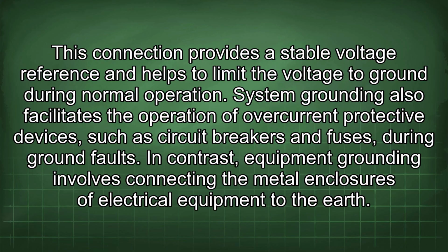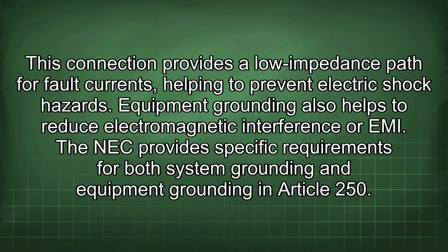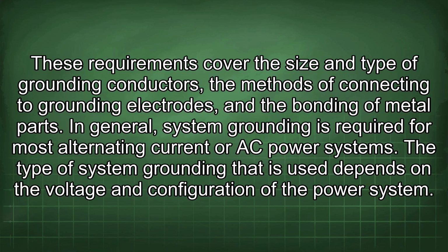In contrast, equipment grounding involves connecting the metal enclosures of electrical equipment to the earth. This connection provides a low impedance path for fault currents, helping to prevent electric shock hazards. Equipment grounding also helps to reduce electromagnetic interference, or EMI. The NEC provides specific requirements for both system grounding and equipment grounding in Article 250. These requirements cover the size and type of grounding conductors, the methods of connecting to grounding electrodes, and the bonding of metal parts. In general, system grounding is required for most alternating current or AC power systems.